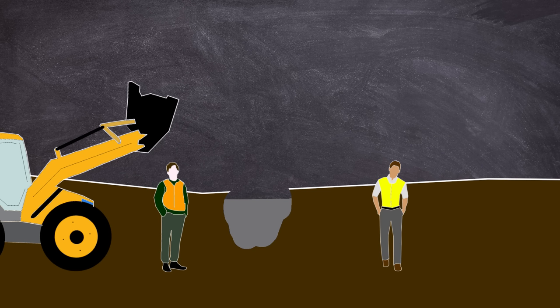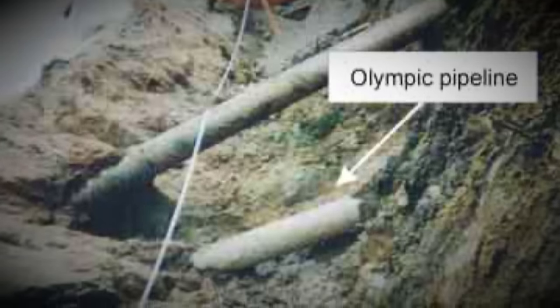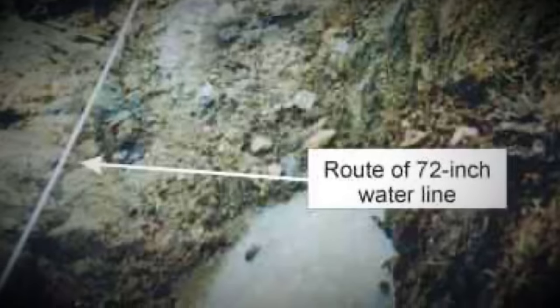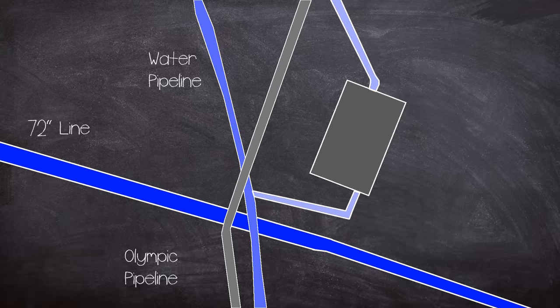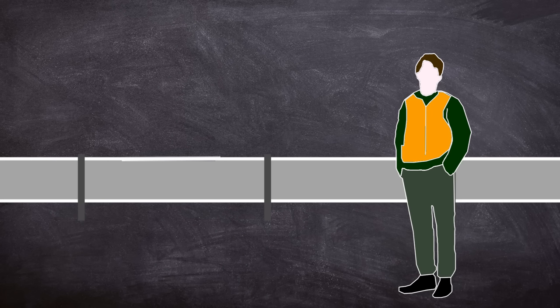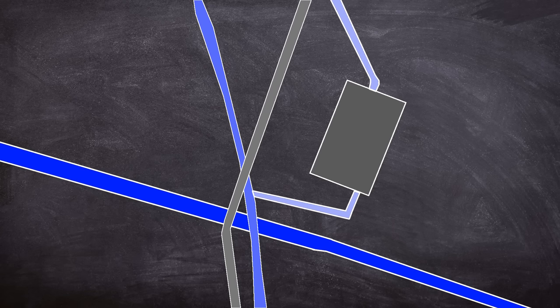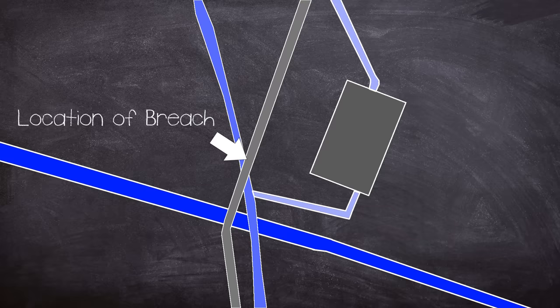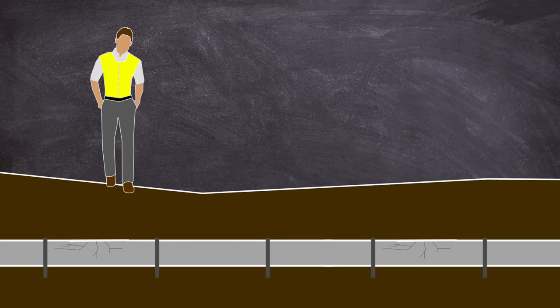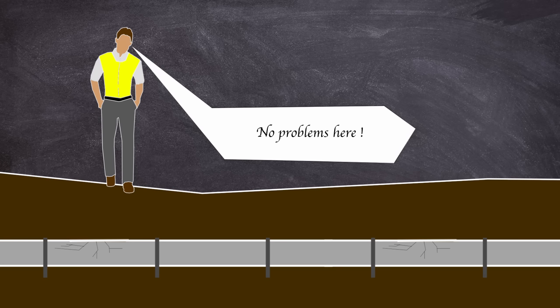More duct and pipework was installed during the water plant upgrade, with most but not all the days being witnessed by an Olympic employee. On the 11th of August 1994, several witnesses noted the pipeline being struck 17 feet north of the centerline of the T connection. Although Olympic was not informed of this, personnel coated the area of the pipeline that had been struck with a mastic coating before backfilling over it. When looking at a diagram of where the rupture happened, we could see that the works for the water treatment plant and the strike location match up. The pipeline was inspected between 1991 and 1999 and anomalies were discovered in the area of the waterworks, but no remedial action was undertaken.